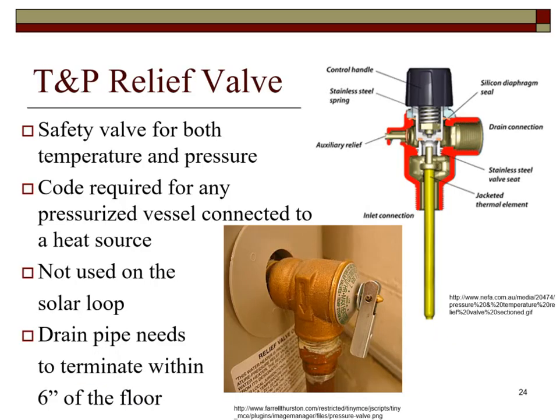A temperature pressure relief valve is also called a pressure temperature relief valve, or P&T valve, or T&P valve. These names are used interchangeably in the industry. This valve, shown, protects system components from excessive pressures and temperatures. A pressure temperature relief valve is always plumbed to the solar storage as well as the auxiliary tank.